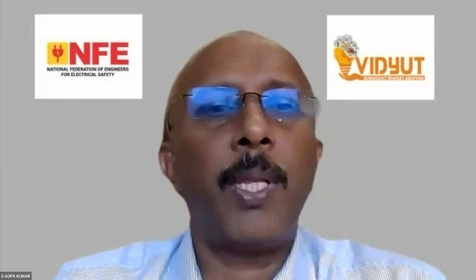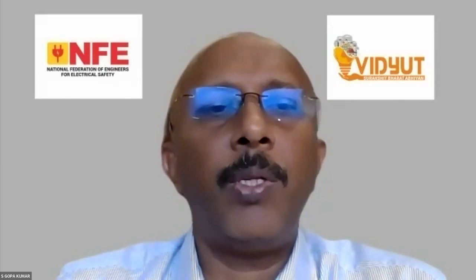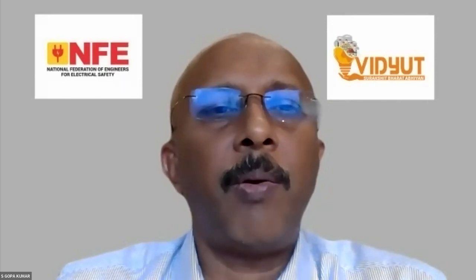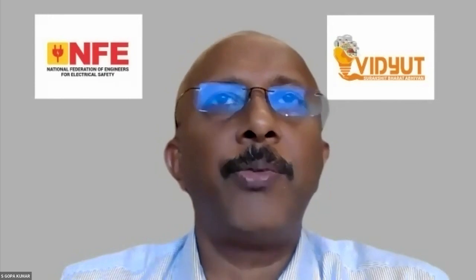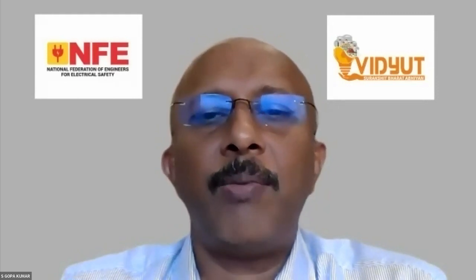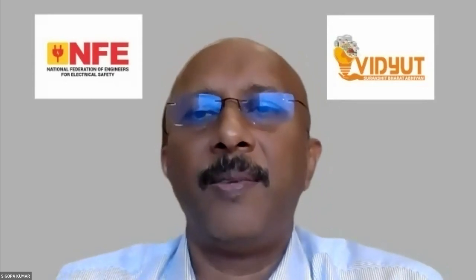Okay, this is to Amaya. Amaya, you talked about the plug. What kind of plugs are supposed to be used on medical equipment in ICUs? IS 1293, IEC 60309, or is there any special standard altogether? To my knowledge, there is no special standard. It is the normal Indian standard plug and socket. Here, the problem is the plug is of one standard and the socket is of another standard. Both plug and socket must be of the same standard. If you are using a German socket everywhere, then the plug also should be of German standard. But the most important thing is you are not supposed to use a German socket in India. It should be as per the Indian standard. And also use a converter which is up to standard.